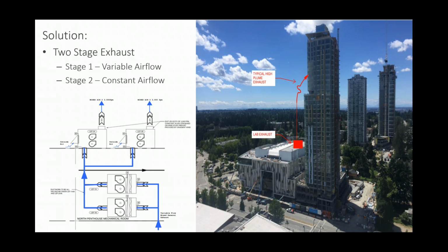And the big thing that we saw when we did our wind study was, based on what's in this photo, you see the lab exhaust there, and we looked at high plume exhaust. The high plume exhaust basically took all that dirty lab air and wrapped it with a bunch of clean air on the outside of that lab exhaust air, and it went up about 20 stories and just hit the building with all of those chemicals still in a big plume of air. So it was probably the worst way we could exhaust out of this building.